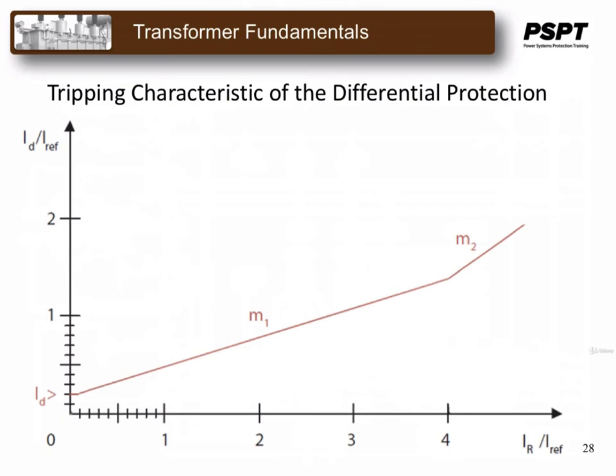diagram. The MiCOM P63 series differential protection devices are provided with a saturation discriminator that allows for such things as the startup of directly switched asynchronous motors that could cause transient transformer saturation. Restraint under inrush conditions is based on the presence of second harmonic components in the differential currents. For restraint under overfluxing conditions, the ratio of the fifth harmonic to the fundamental wave for the differential current of the measuring system serves as the criterion. Zero sequence filtering may be deactivated separately for each winding in the case of an operational grounding within the protected zone.